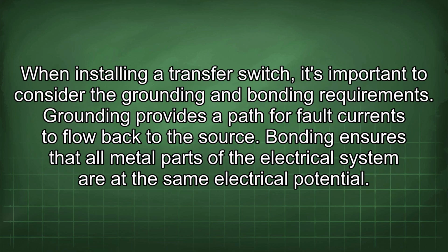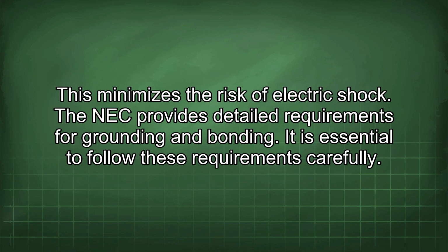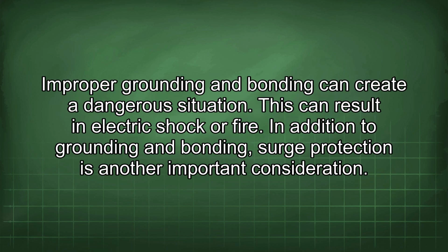When installing a transfer switch, it's important to consider the grounding and bonding requirements. Grounding provides a path for fault currents to flow back to the source. Bonding ensures that all metal parts of the electrical system are at the same electrical potential. This minimizes the risk of electric shock. The NEC provides detailed requirements for grounding and bonding. It is essential to follow these requirements carefully. Improper grounding and bonding can create a dangerous situation. This can result in electric shock or fire.